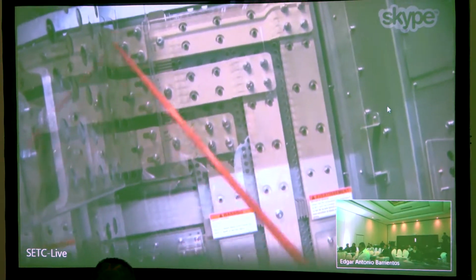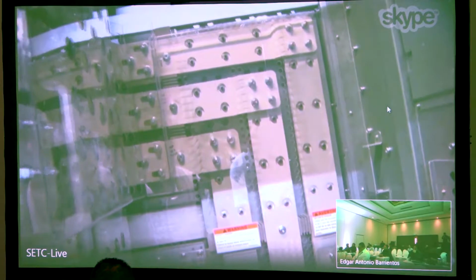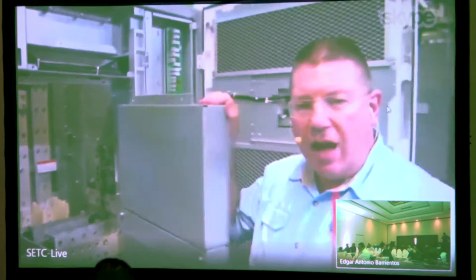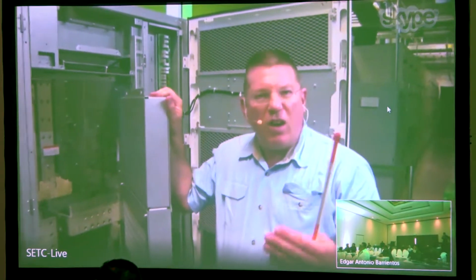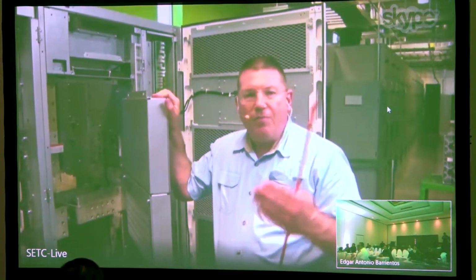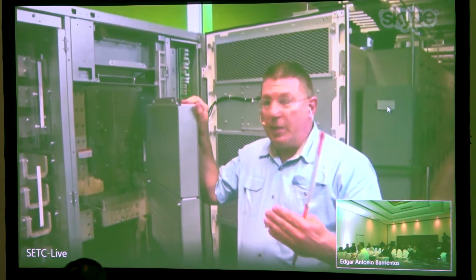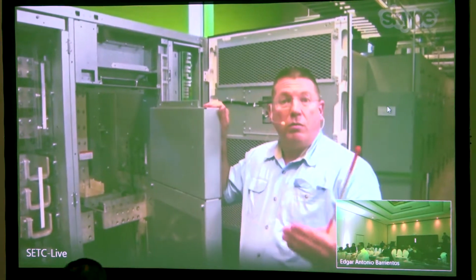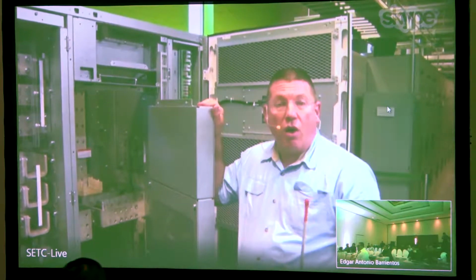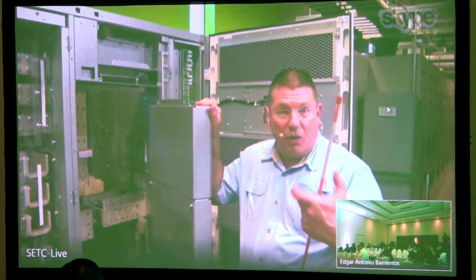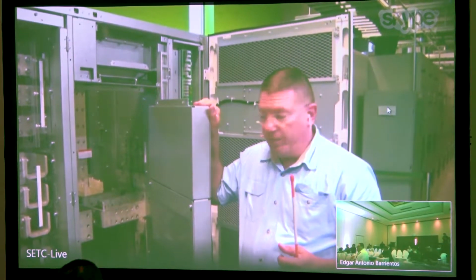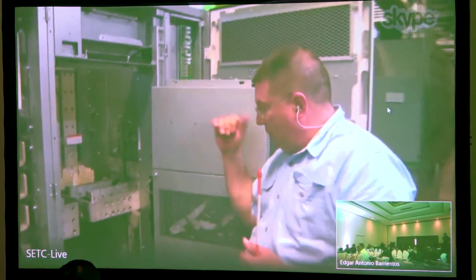Now, we mentioned single mains. If we can see back here, there's busing that goes back for the single mains kit, and that's unique to this 750 cabinet. On the 1000 and the 1500 IOC, that busing configuration is going to be a little bit different, but it's the same idea. It's basically 6 bolts per bus that are installed so that we can tie that input to the static bypass input.